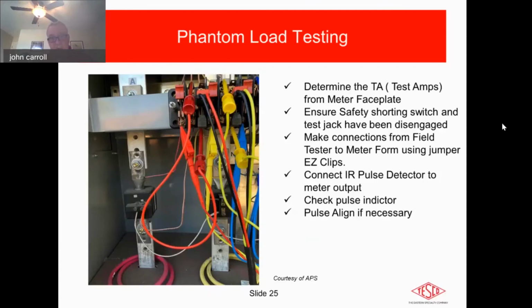When you get familiar with this equipment, you can set this up and run a test. It takes no longer than about 30 minutes to run this test. It's not a race. I'm not suggesting it is, but that's important to know that it's not a long-term half-day test. It can be done very quickly. You can put the instrument back in, close the lid, put the instrument back in the truck, run to the next site. It's all run on batteries.